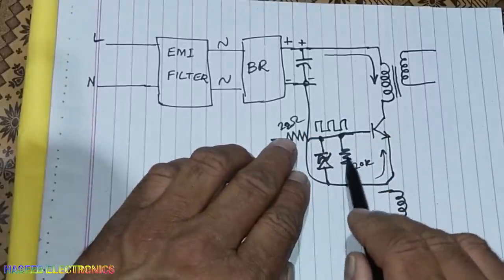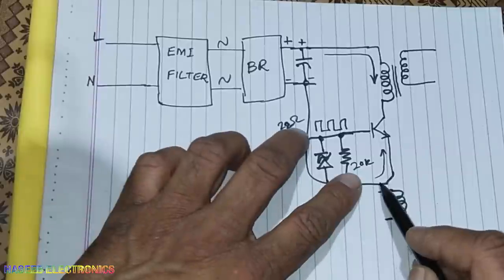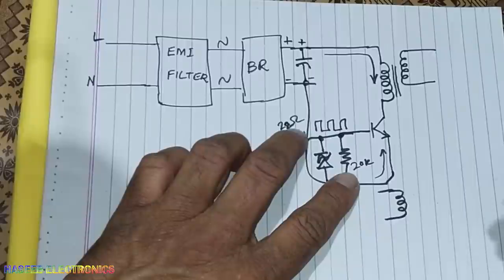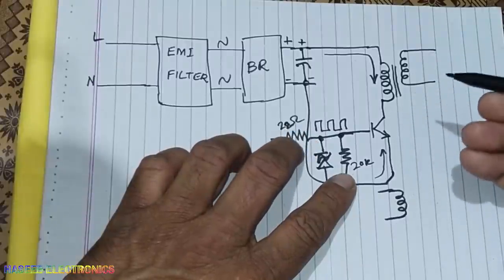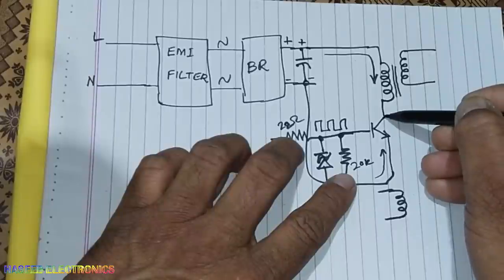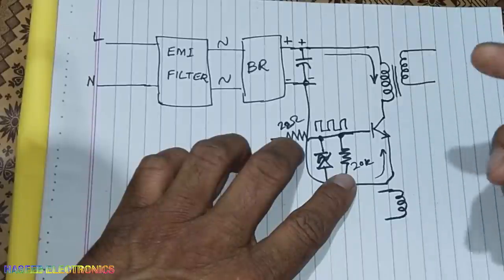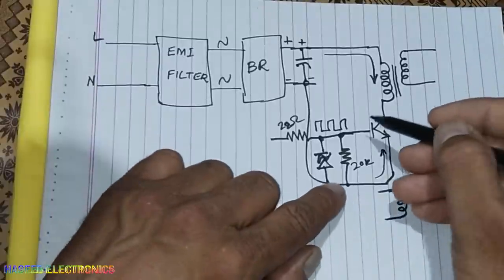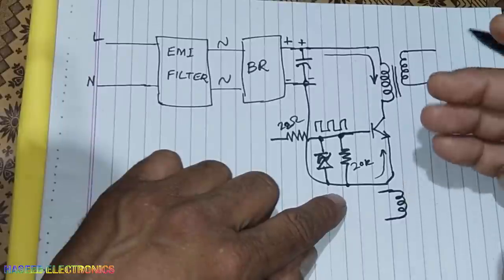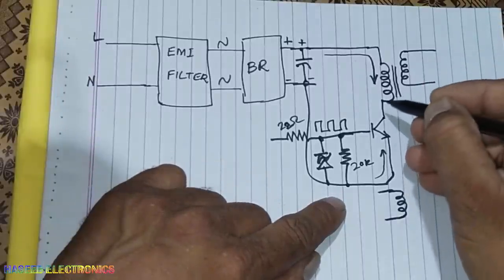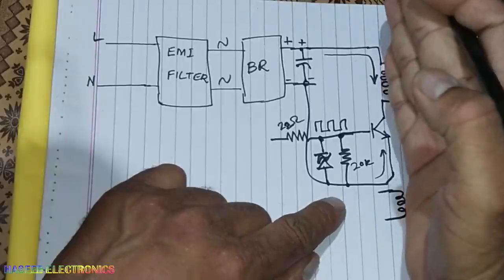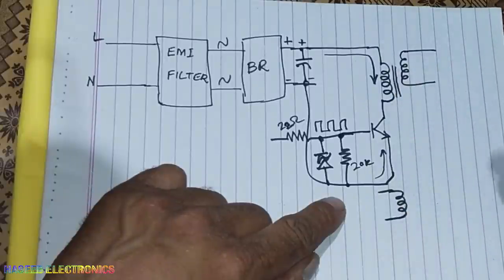If the voltage is not turning on properly due to some problem in these components, or material failure, it is providing some resistance. Sometimes, because it is a heat-generating component, its joints on the PCB are dry-soldered, so the contact resistance is increased. This can also cause a reduction in current flow. Reduced current flow will not allow the magnetic field to build properly, so the voltage will not transfer to the secondary properly.